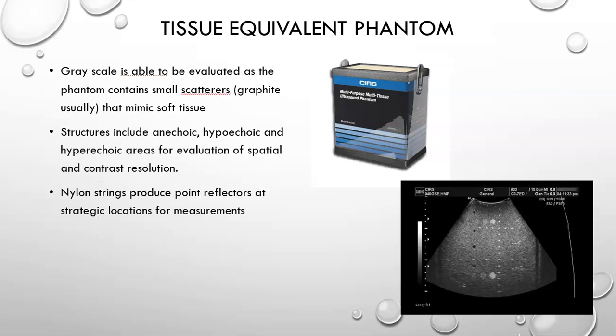The grayscale is able to be evaluated as the phantom contains many small scatterers, which look like soft tissue. These are usually made of graphite and added to the texture. The structures include anechoic areas, hypoechoic areas, and hyperechoic areas, so that we can evaluate not only spatial resolution but contrast resolution also. The nylon strings that are used to show spatial resolution are also good point reflectors that can be used for measurements that require point reflectors.